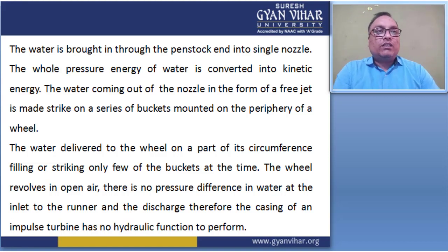The water is delivered to the wheel on a part of its circumference, striking only a few of the buckets at a time, and the wheel revolves in open air. There is no pressure difference in the water between the inlet to the runner and the discharge. Therefore, the casing of an impulse turbine has no hydraulic function to perform. So these are the different points related to the Pelton wheel turbine.